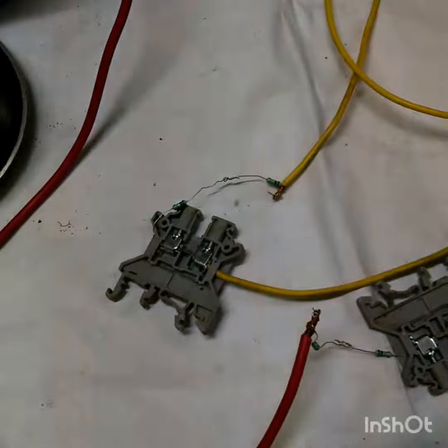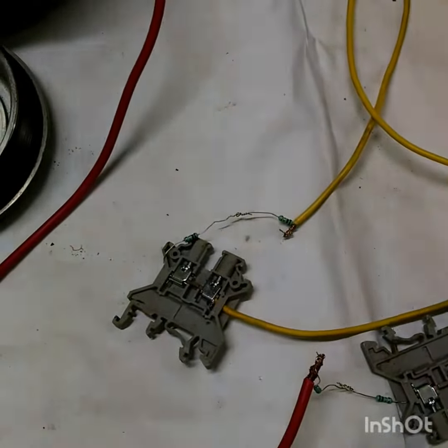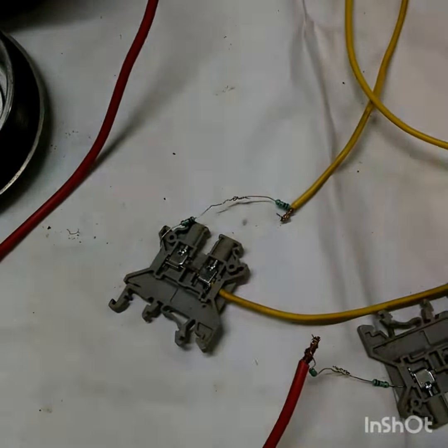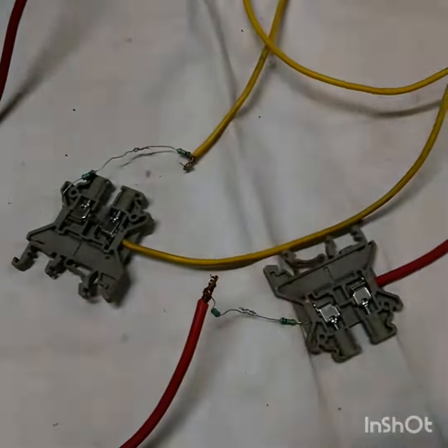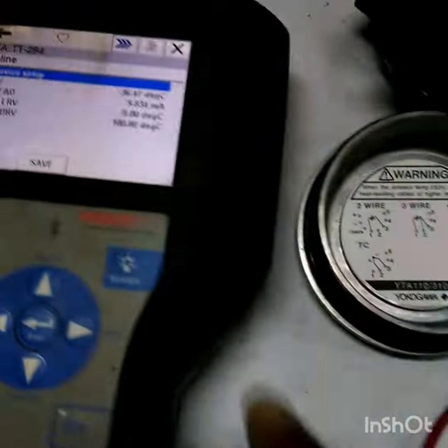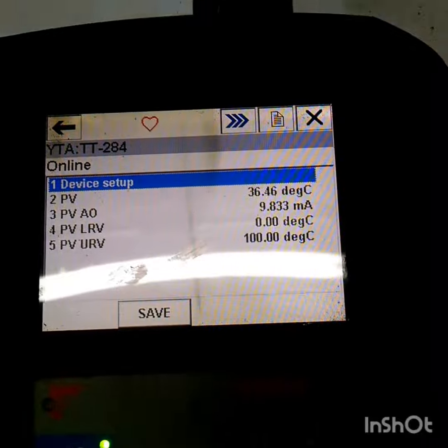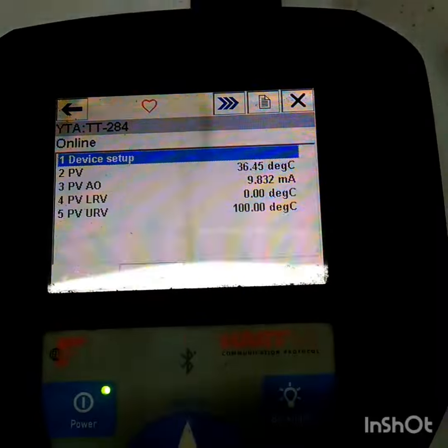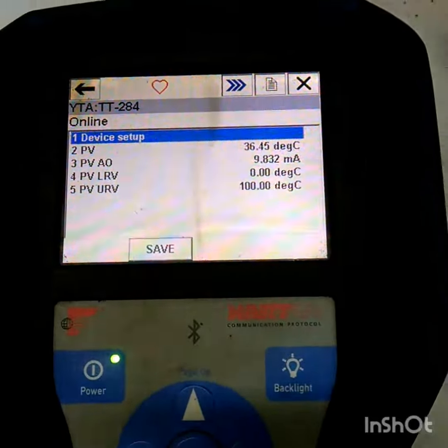That's around 4.3 ohms for both resistors combined, causing more than 10 degrees centigrade of error. So I will now configure this transmitter to three-wire, since I already have another resistor added for the third wire.